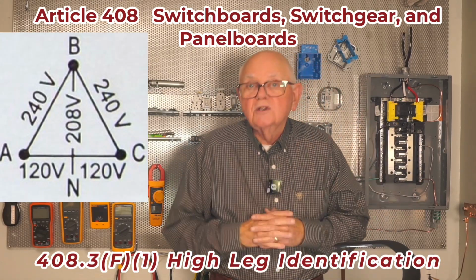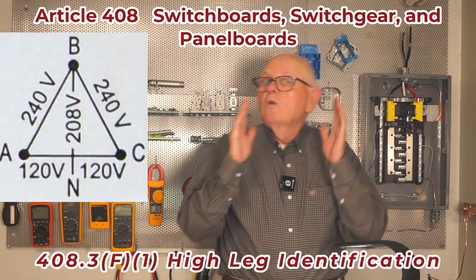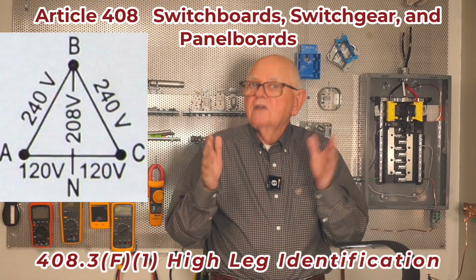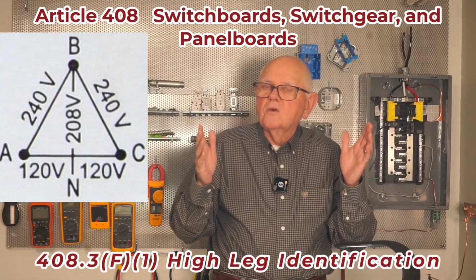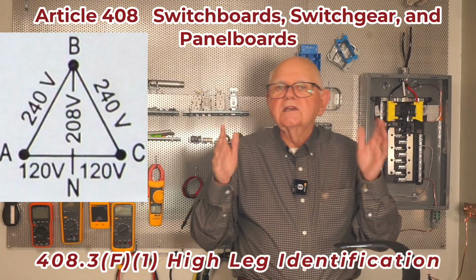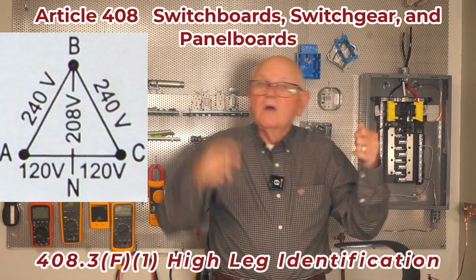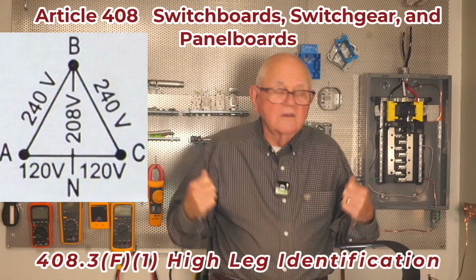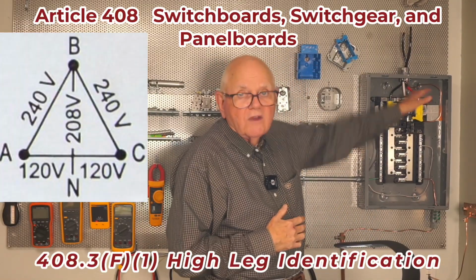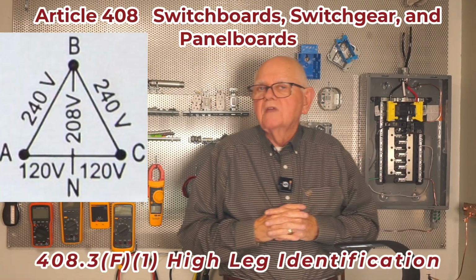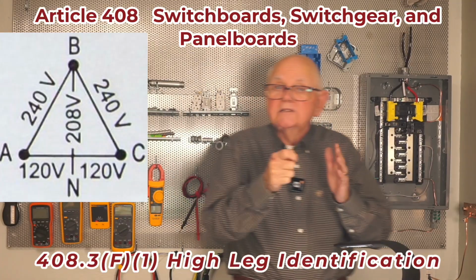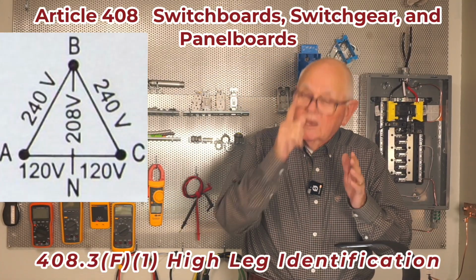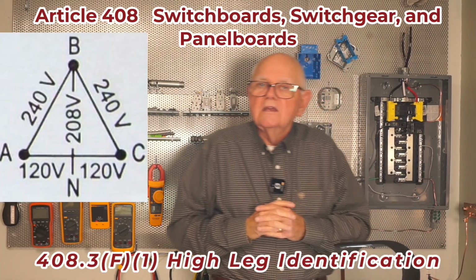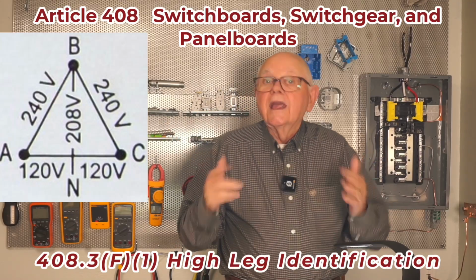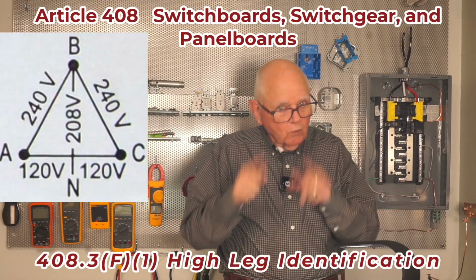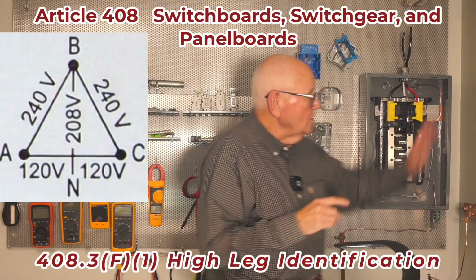I would go to one of those phases on the secondary side, and I could connect a red wire and a black wire to each end of one phase and bring that in, and that would be my ungrounded conductors coming into my panel board. I could go right to the center and attach another wire, and I would also ground that connection. So now I'd have a grounded conductor. By definition in Article 100, it would be a neutral.